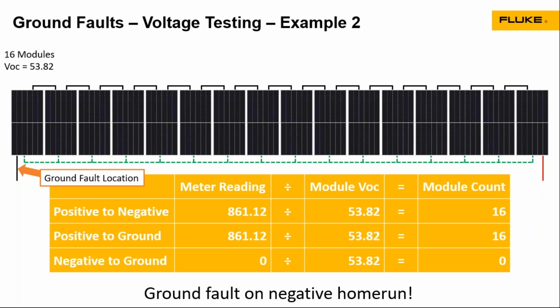It can also be much more challenging to troubleshoot because I most likely have a very long wire between the end of the string and the combiner box or the inverter. It may be in a conduit or in some type of trough, and I've got to go through and find that wire and trace it down and figure out exactly where the ground fault is. So when doing this type of testing, don't miss this type of situation. It can be easy to overlook if you're not paying close attention.